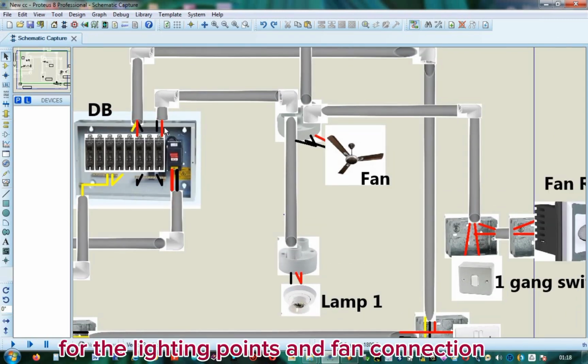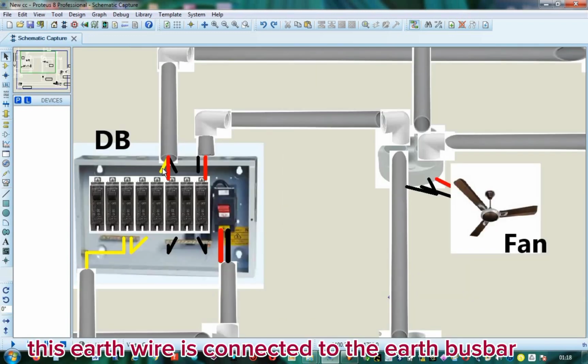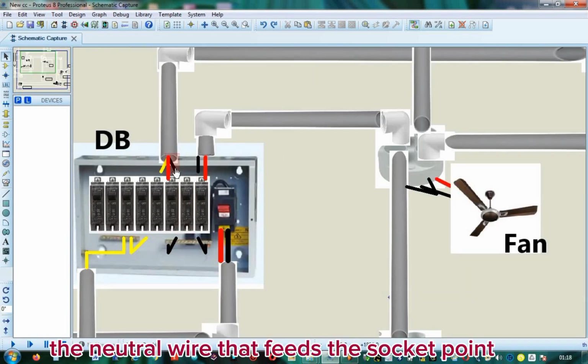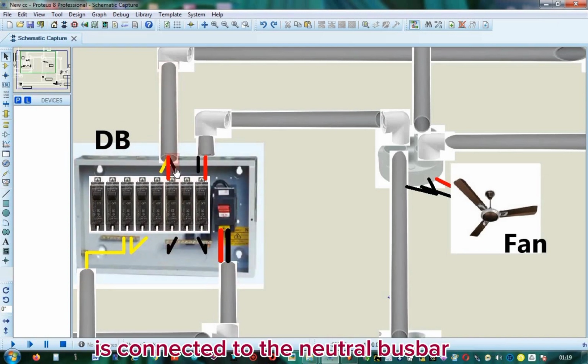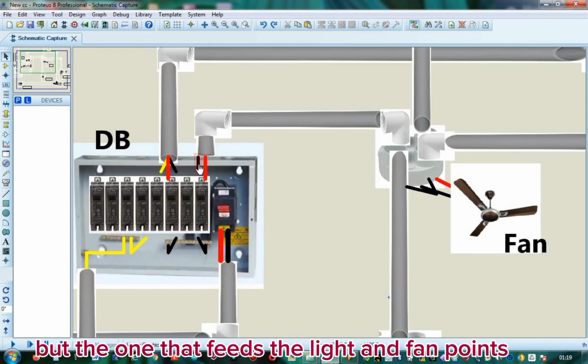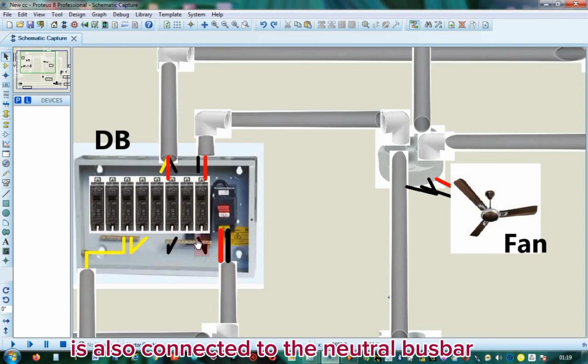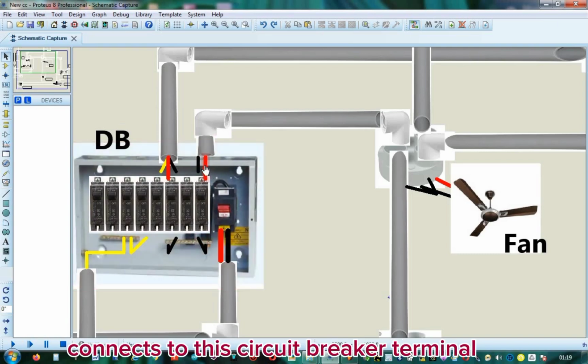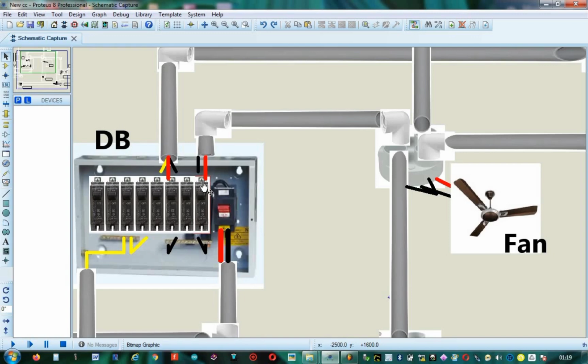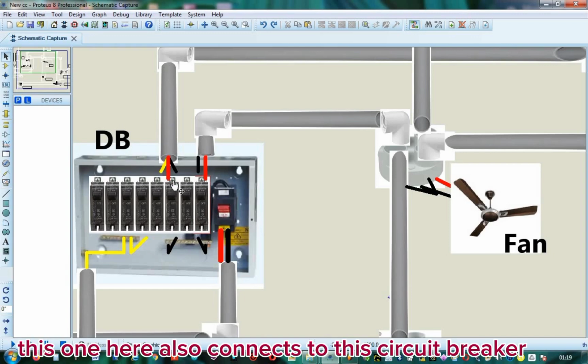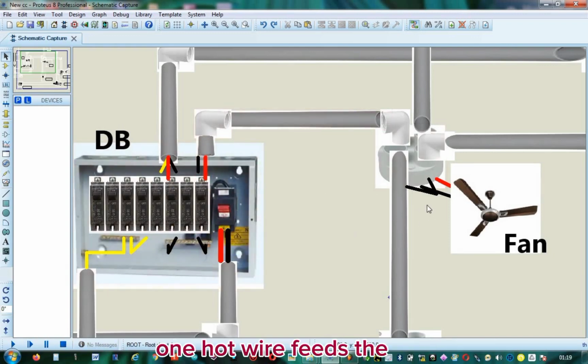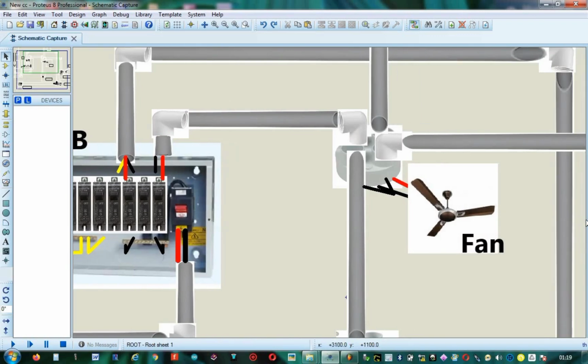For the lighting points and fan connection, we have 1 hot wire and a neutral wire. This earth wire is connected to the earth bus bar. The neutral wire that feeds the socket point is connected to the neutral bus bar, while the one that feeds the light and fan points is also connected to the neutral bus bar. This hot wire connects to this circuit breaker terminal. This one here also connects to this circuit breaker. 1 hot wire feeds the fan point and the light points.